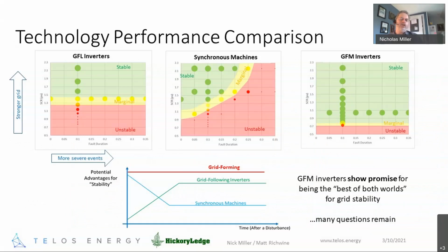This is a bit of an eye chart. We were inspired by John O's world-changing J curves and thought we'd try to get some visuals here you could take away without being buried in wiggles and numbers. On the left is a stability regime reflected in the outlines of the previous slides, and you see a bunch of dots, those are cases run for a primary clearing time of 100 milliseconds. The y-axis, though small, is the grid strength, the short circuit ratio. As you'd expect, as the grid gets stronger, the cases are more stable.